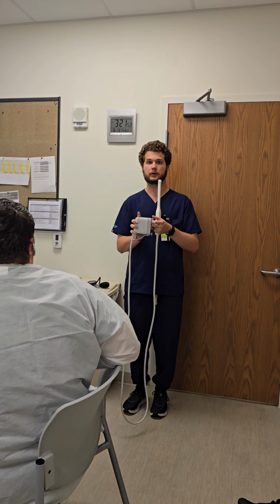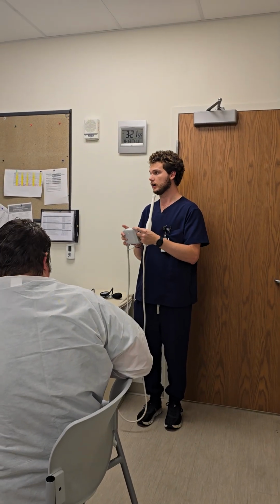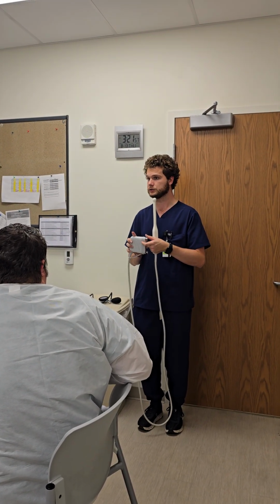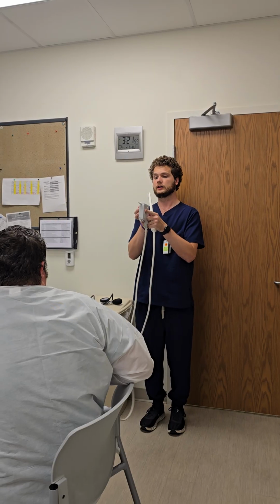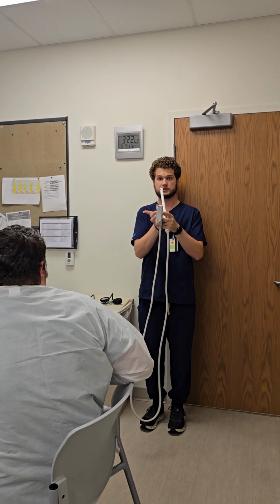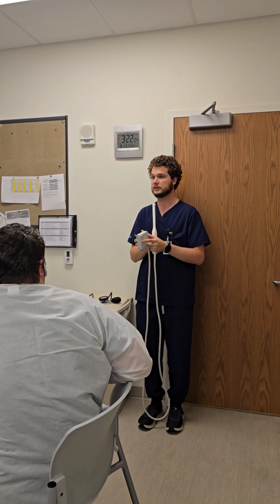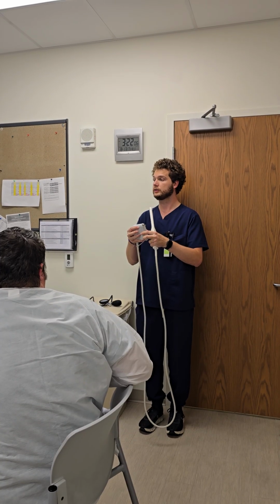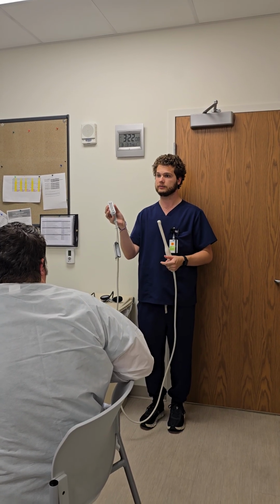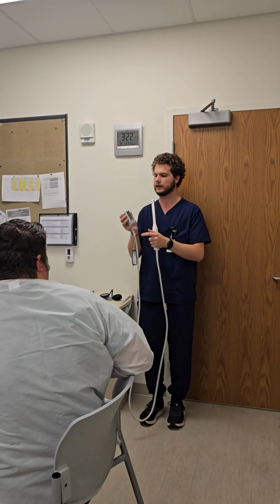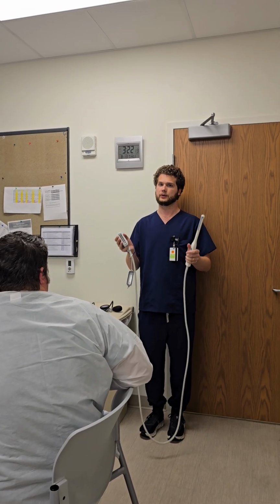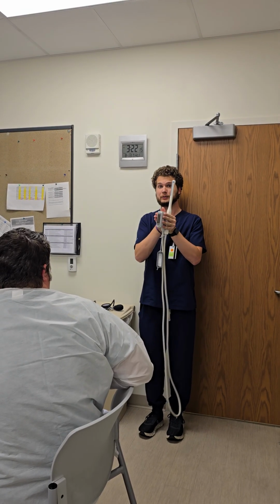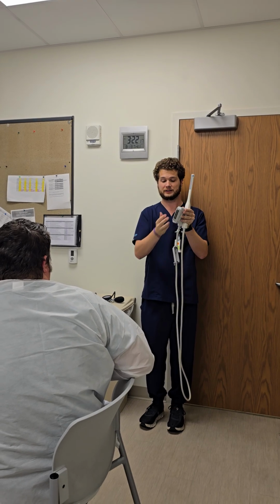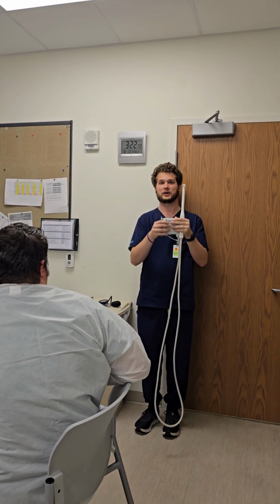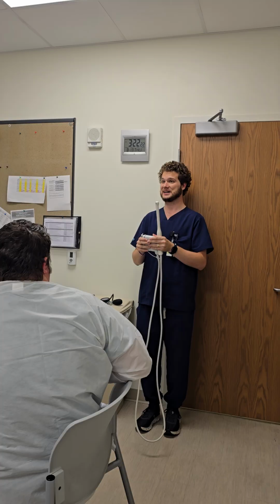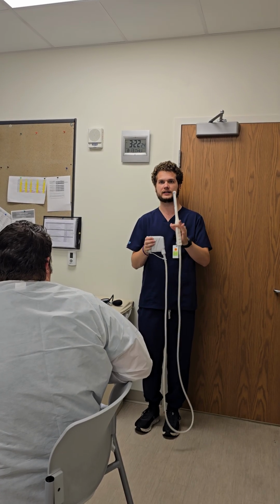Now that's just for the hand wash. When we're going through the V-Pro, we want to take the cap off. If this cap is all the way on and goes through V-Pro, what's going to happen is, this is going to look like a goldfish. It's going to pop. Won't fit in the machine, won't work anymore. So make sure when we put it through the V-Pro, we take the cap off. And just make sure it's not wet on the inside or around it. Just wipe it down with a towel and put it through the V-Pro. But cap off for V-Pro, cap on for hand wash. I cannot emphasize that enough. I think it's all built into the directions.